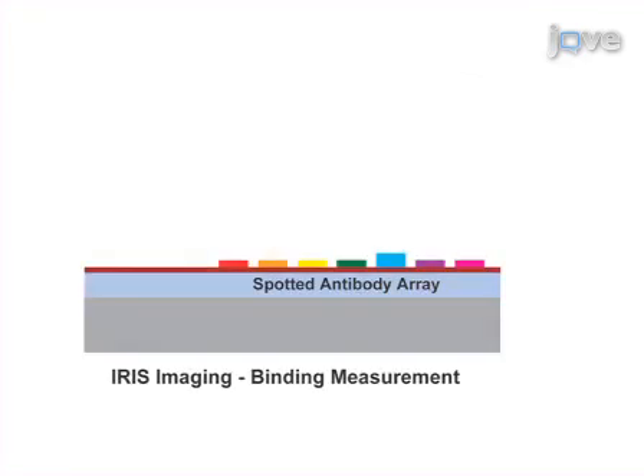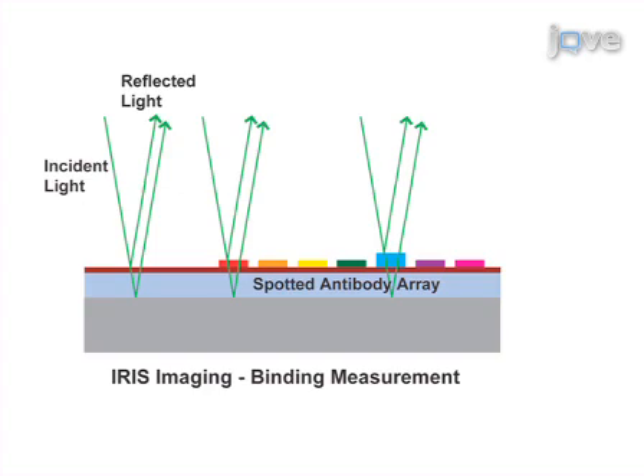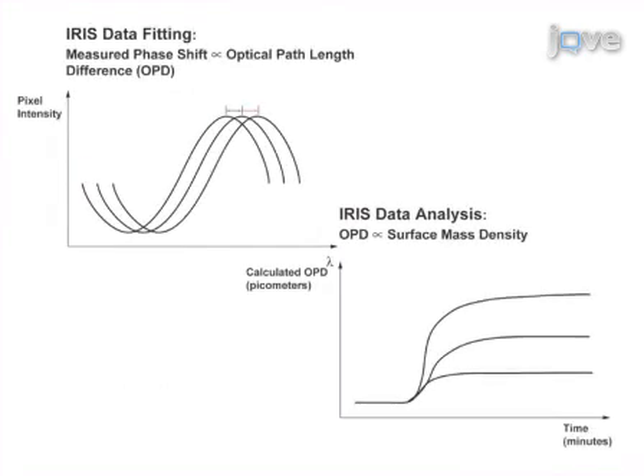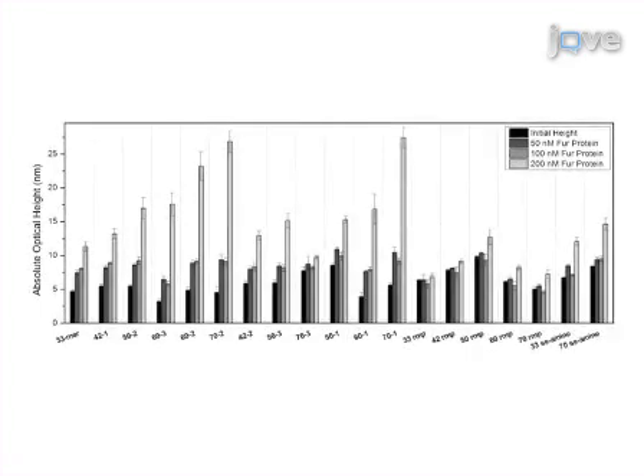Next, the entire sensor array is imaged at different wavelengths of light with the IRIS system. The reflected intensities for each pixel are processed with custom-coded algorithms in order to quantify the amount of biomaterial bound to each test or control condition post-incubation. Results are obtained that show effective detection and absolute quantification of antibodies in a complex mixture based on the interferometric, label-free measurements of this system.